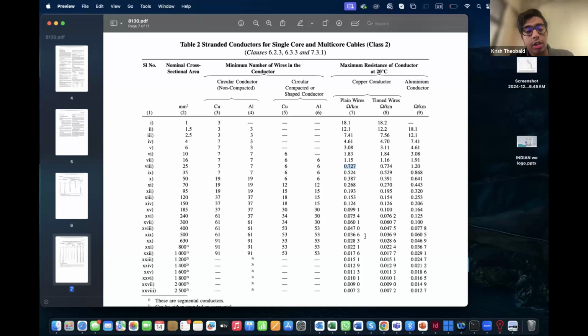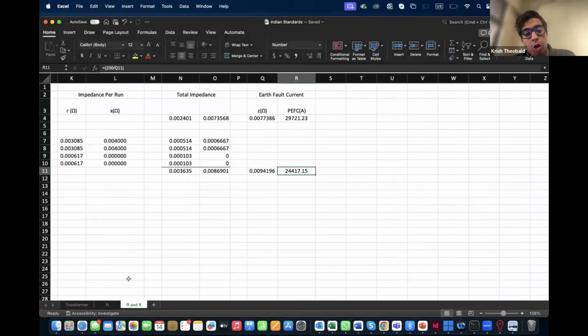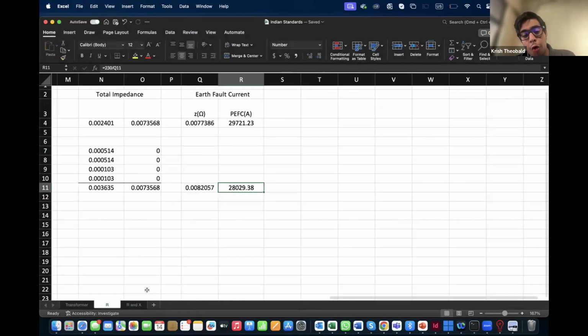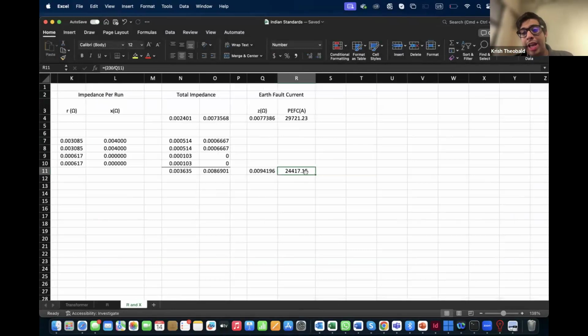This is very important because currently we are not doing this. As you can see, this causes a gross oversizing of protective devices, which will increase costs. The other implication is that you may think you have 28 kA of current available to cause automatic disconnection, whereas actually you have only 24. So your devices may not disconnect. At this fault current this is less likely, but further down it may be a significant problem. Anyways, I hope that answers the question.